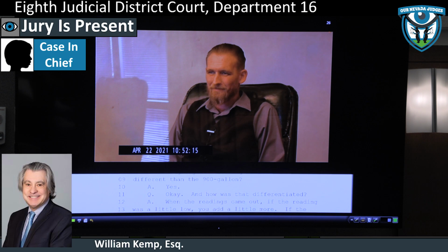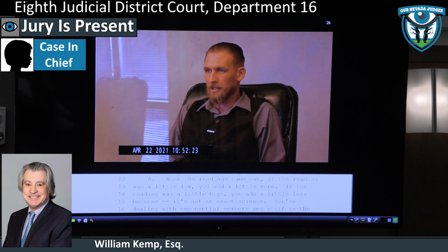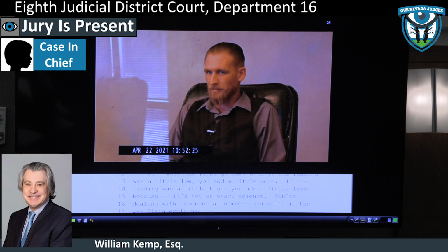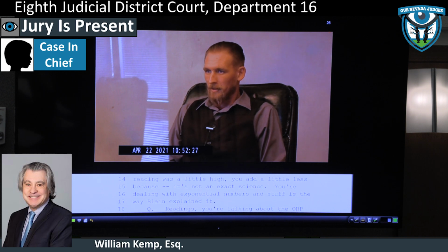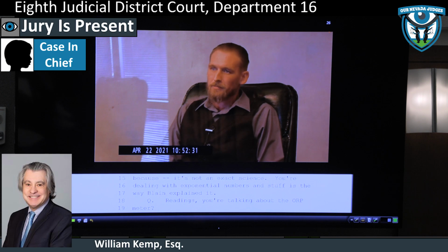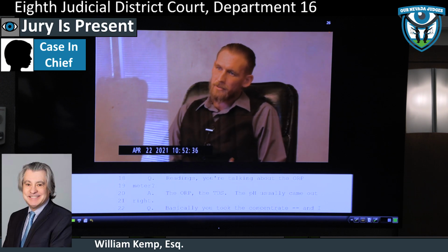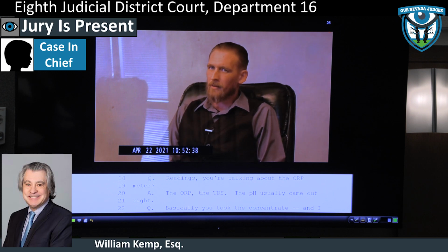Okay. And how was that differentiated? When the readings came out, if the reading was a little low, you added a little more. If the reading was a little high, you added a little less, because it's not an exact science. You're dealing with exponential numbers and stuff, is the way you explained it. And when you say readings, you're talking about the ORP meter. The ORP, the TDS, the pH usually came out right.